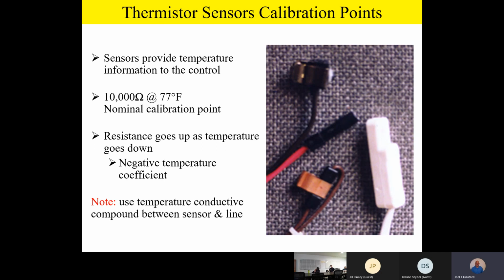Now, it should be noted these sensors are negative coefficient, which means that the resistance goes up as temperature goes down, which is exactly opposite of what we call a positive coefficient resistor or thermistor, where as the temperature goes up, the resistance goes up. This is exactly opposite. The warmer it gets, the lower the resistance. So resistance goes up as temperature goes down.